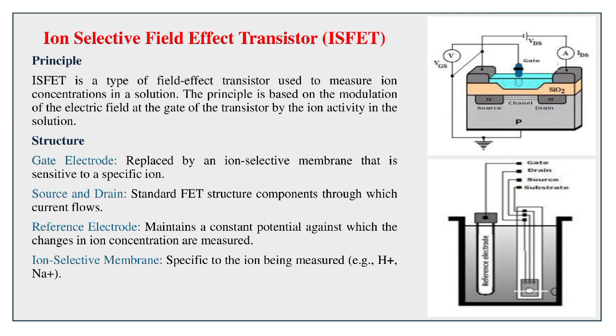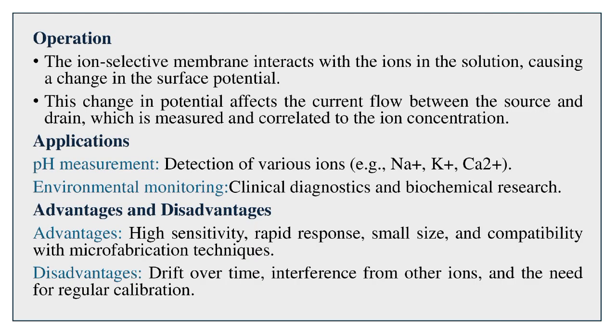ISFET Structure. Gate electrode: replaced by an ion-selective membrane that is sensitive to a specific ion. Source and drain: standard FET structure components through which current flows. Reference electrode: maintains a constant potential against which changes in ion concentration are measured. Ion-selective membrane: specific to the ion being measured and correlated to the ion concentration.